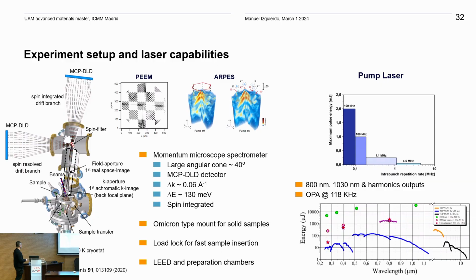The important thing to know is that it's equipped with a momentum microscope provided by the group of Gerd Schönhense, as I told you before. So basically, this allows you to do either microscopy in PEEM mode or angle-resolved photoelectron spectroscopy, and for this reason we call them momentum microscopes. They have a large acceptance angle in the order of 40 degrees. In order to do pump-probe experiments, we have an MCP DLD detector. There is this k resolution. The energy resolution is in the order of 130 meV, and for the moment we have spin integrated only.